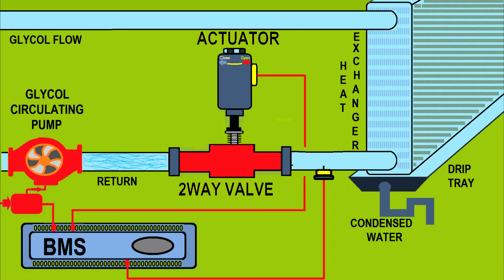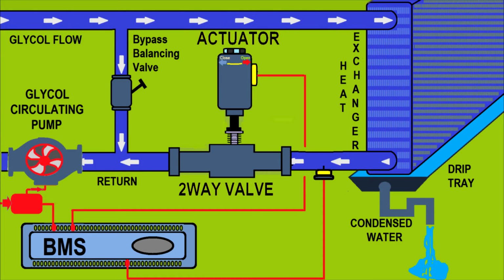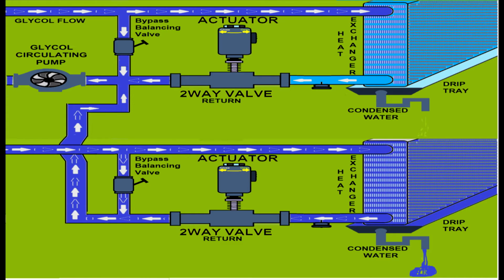But even if you interlock it and you don't have a flow switch to stop the pump, then the pump will still be activated by the interlock. This is the better situation, as I said. If you have a broken valve or something, the glycol will go through the balancing valve. Usually we're using this system for multiple heat exchangers, like you see in this video. We have two heat exchangers on the right hand side. One is warmer, the lower one is cooler, runs below the dew point. It removes water, moisture from the air. The top one just cools the air but doesn't remove any moisture.